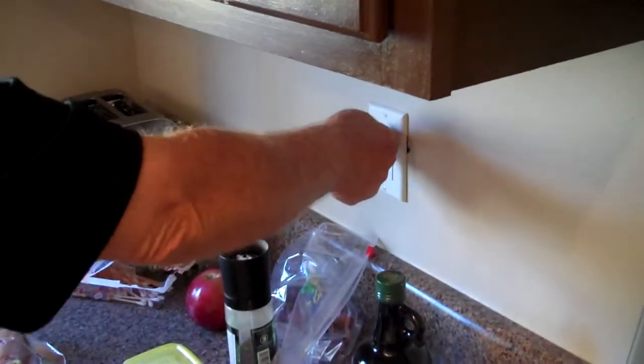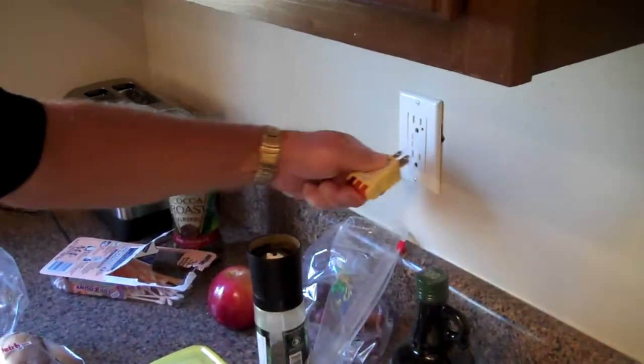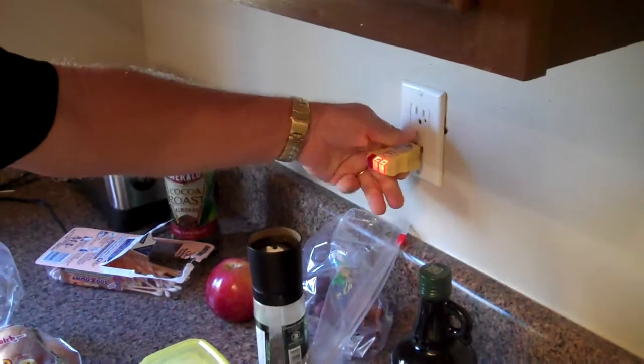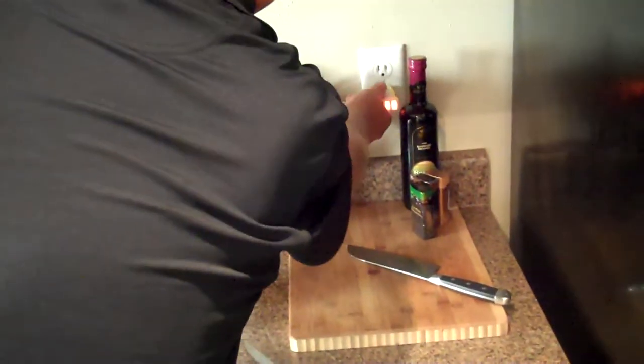And at the same time, while we're on the wall here, we're going to check these receptacles. Any receptacle that we can reach, the tester will tell me exactly if there's a problem — if there's a cross ground going on, reverse polarity. As long as we've got our lights lighting up like that on the right side, we're in good shape right there.